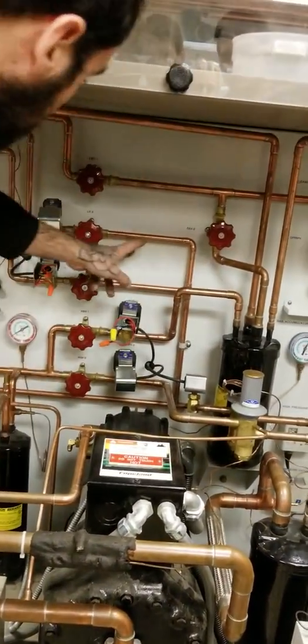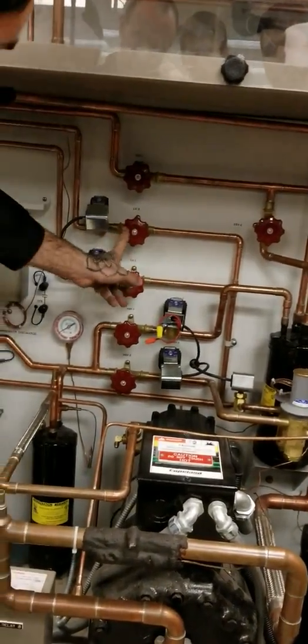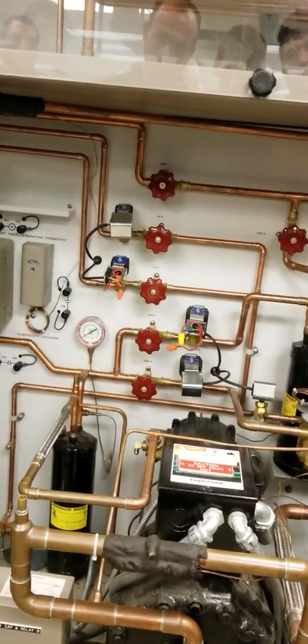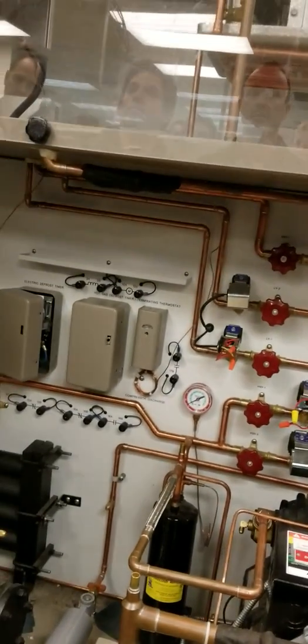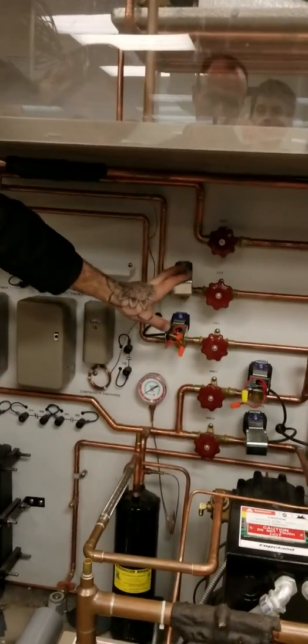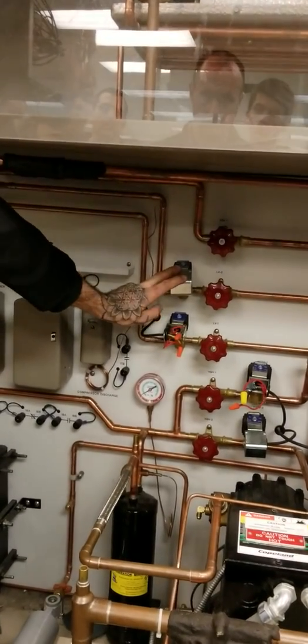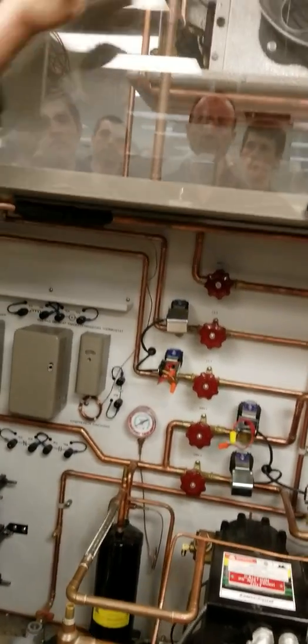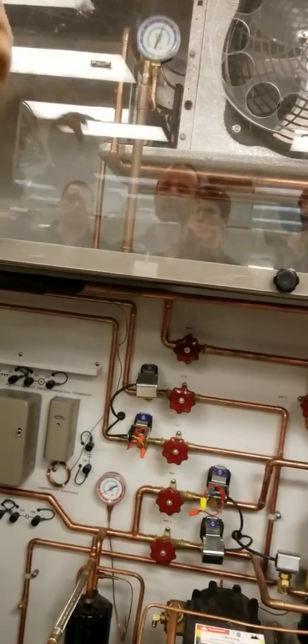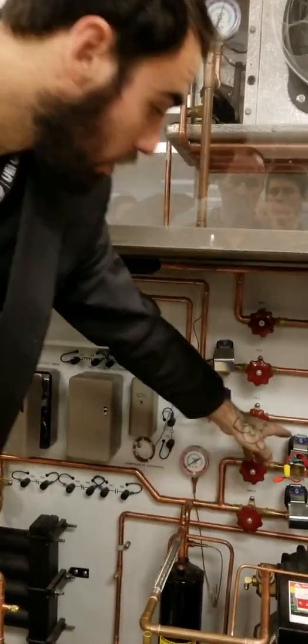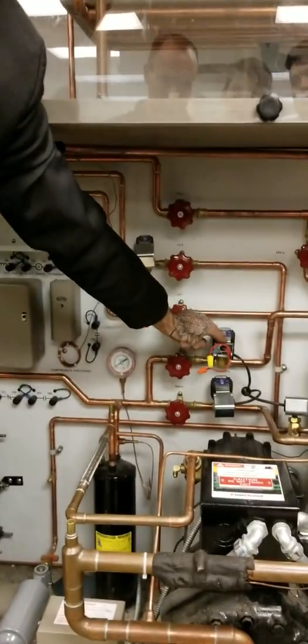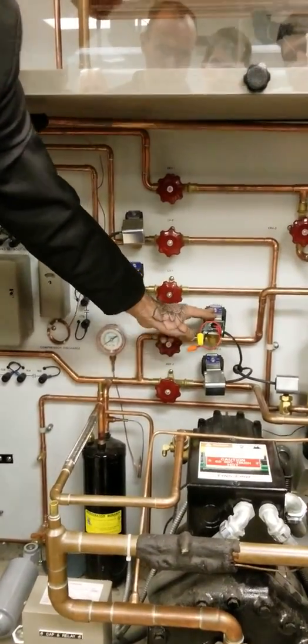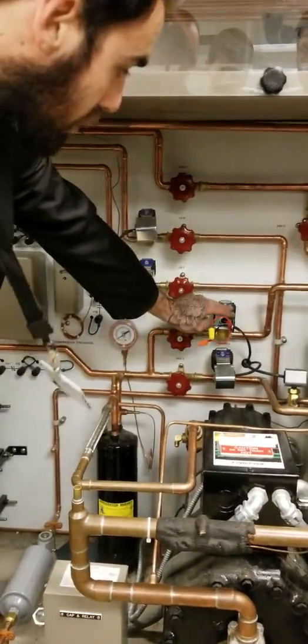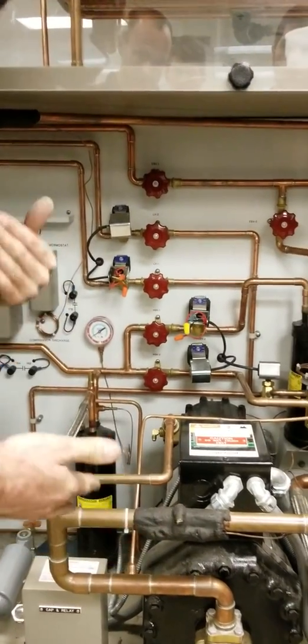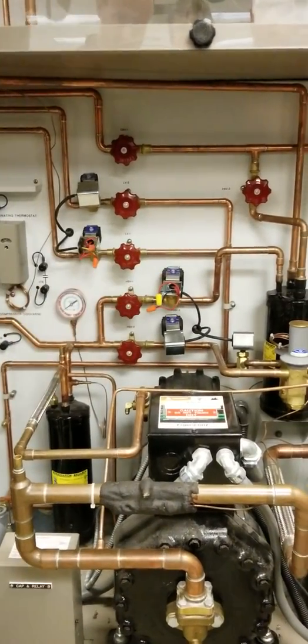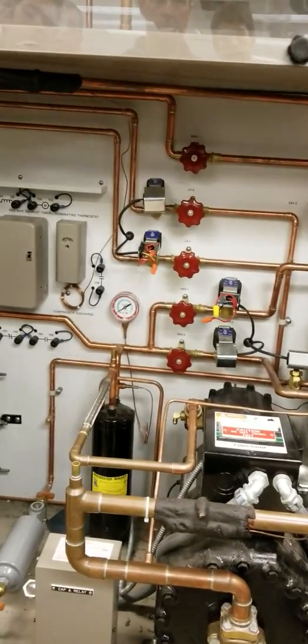So as your refrigerant comes through, it's going to go through the liquid valves. These solenoid valves are going to control when we want to send refrigerant to the evaporators. If one is satisfied, it might close the solenoid valve, therefore closing the refrigerant passage. It loses the magnetism on the solenoid. The solenoid drops, it closes the valve, and now the refrigerant cannot travel to the evaporator that has satisfied load.